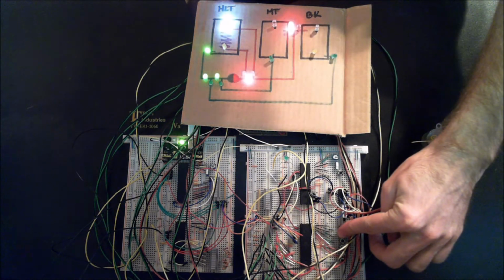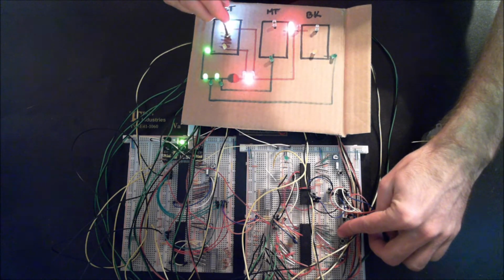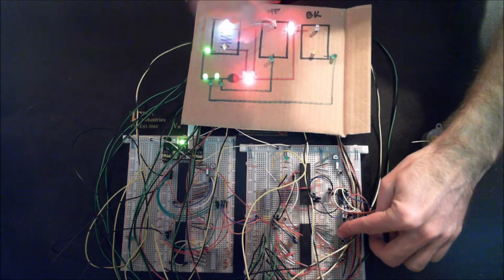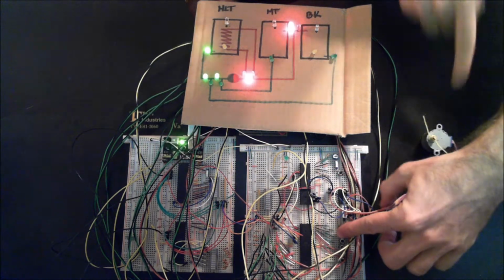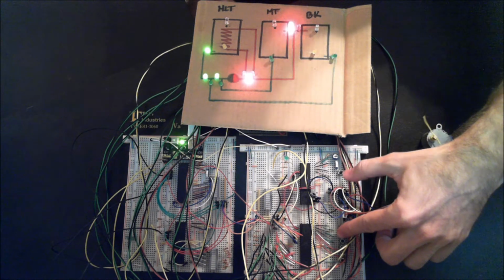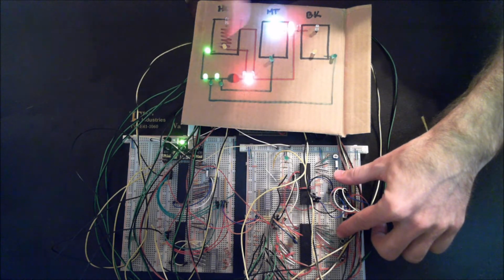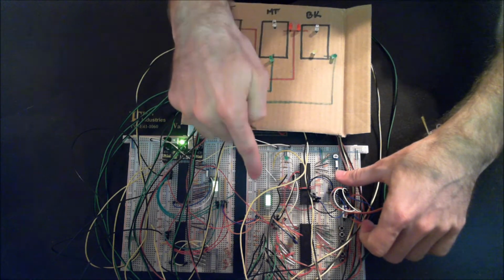Okay, to move water from the hot liquor tank to the mash tun, these valves will be opened, which will begin draining water from the hot liquor tank and filling the mash tun. When the mash tun is not empty, the mixing arm will begin to rotate, maintaining a constant mixing action in the mash tun. When the mash tun is full, these valves will close and a desired temperature will be sent to the mash tun to begin the mashing process.